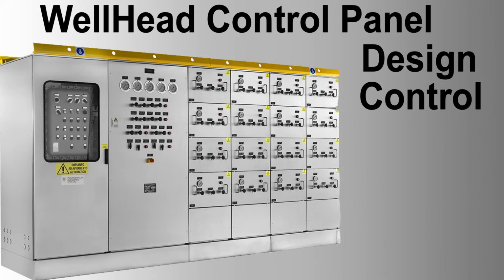Closed-loop control. Definition: closed-loop control systems use feedback from the process output to adjust control actions, ensuring desired performance. Examples. 1. Pressure control loop. Function: maintains wellhead pressure within a specified range. Control device: pressure transducer, control valve. Operation: the pressure transducer measures wellhead pressure and sends feedback to the PLC RTU, which adjusts the control valve to maintain the set point.